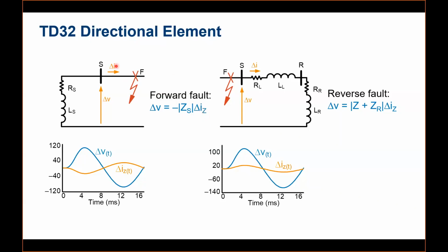So these are derived from delta I. There are some relationships by which you can derive the loop replica currents from the change in currents, but both are analogous. So for simplicity, you can just consider delta I the same as delta IZ. The deciding factor here is the polarity. If they are opposite in polarity, it's a forward fault. If the change in voltage and the change in current are in the same polarity, or in phase, we decide it as a reverse fault.